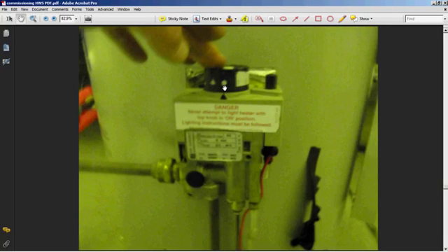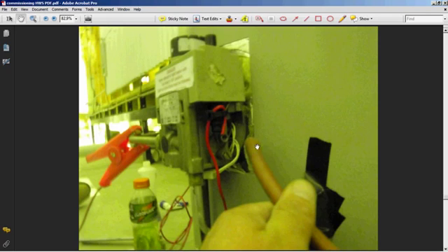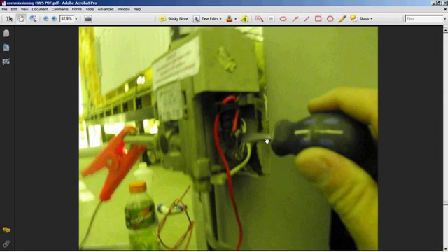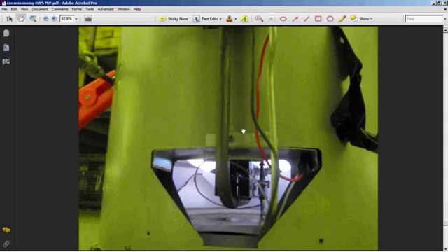Now, disconnect the manometer, turn the unit off, and turn the gas valve off. Disconnect the manometer. Insert the test point screw. Now, relight the appliance, as shown here.